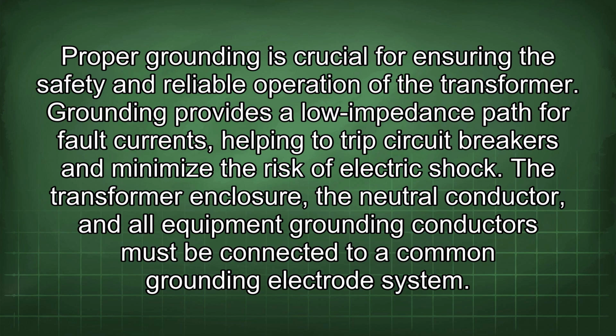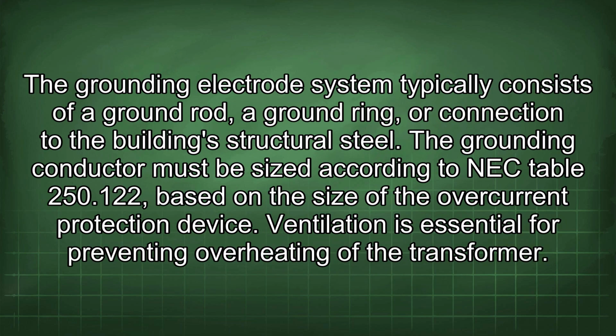Proper grounding is crucial for ensuring the safety and reliable operation of the transformer. Grounding provides a low impedance path for fault currents, helping to trip circuit breakers and minimize the risk of electric shock. The transformer enclosure, the neutral conductor, and all equipment grounding conductors must be connected to a common grounding electrode system. The grounding electrode system typically consists of a ground rod, a ground ring, or connection to the building's structural steel. The grounding conductor must be sized according to NEC Table 250.122, based on the size of the overcurrent protection device.